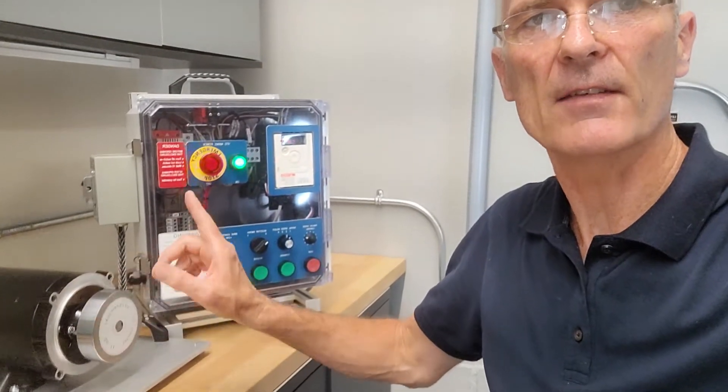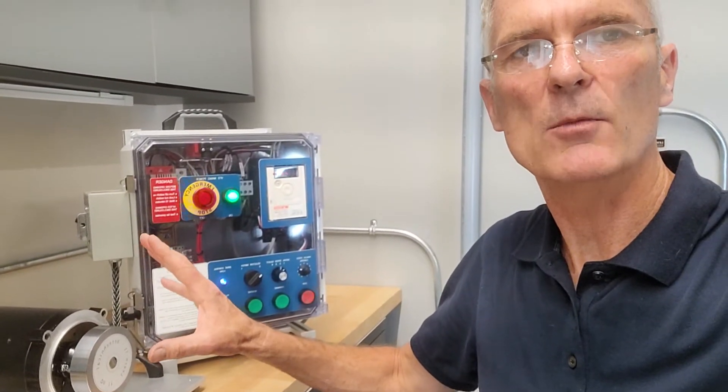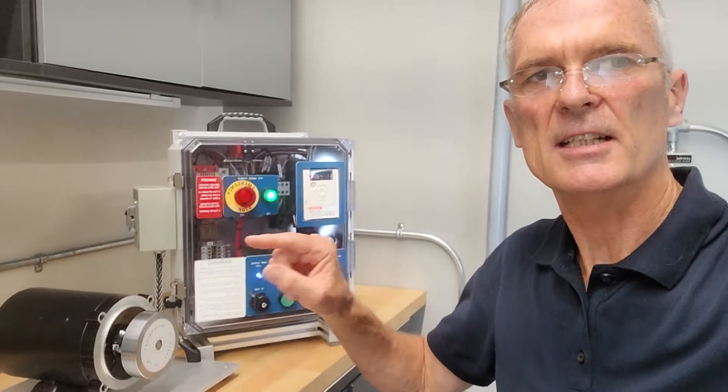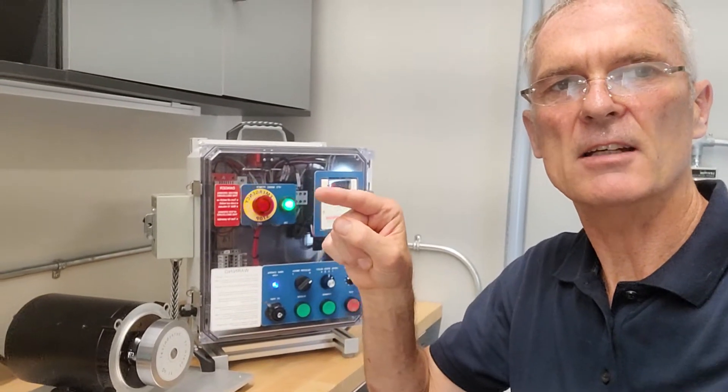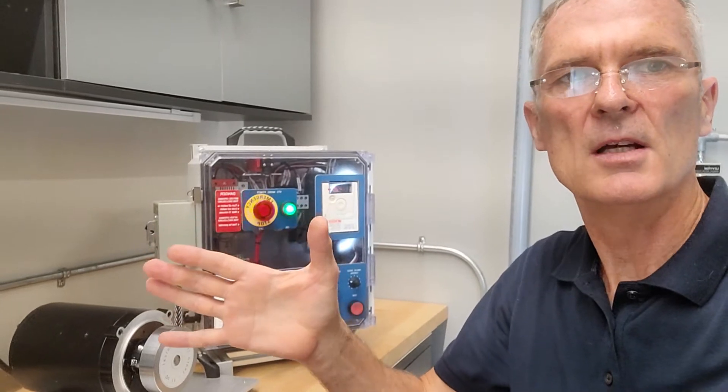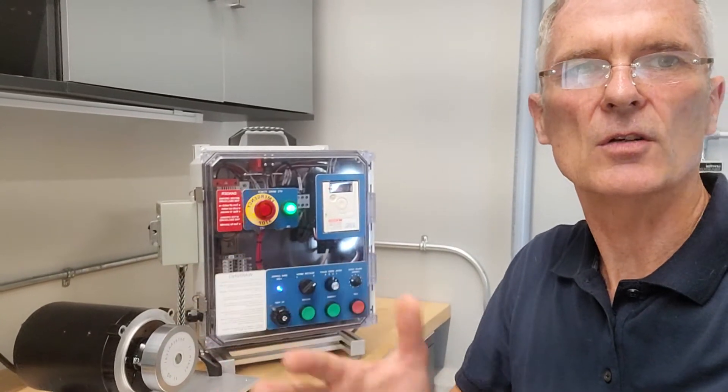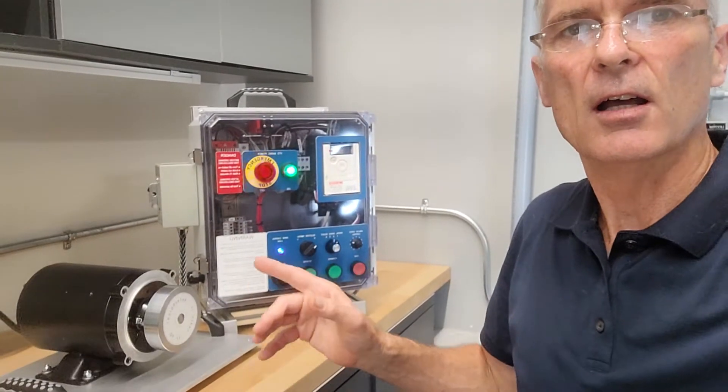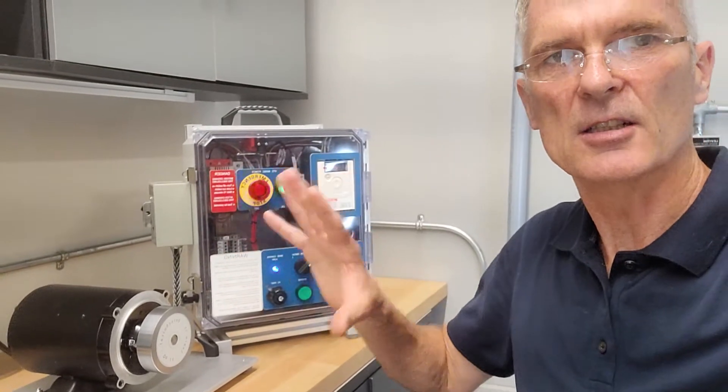Now what drives do - drives have settings, and not all drives are set up the same way. Some drives have a setting that as soon as you hit the stop button you can tell it to start injecting DC, so it will help slow a large high inertia load down fairly quickly.